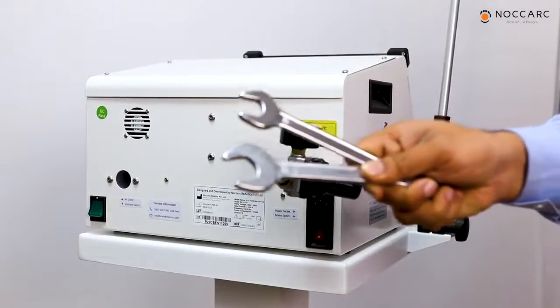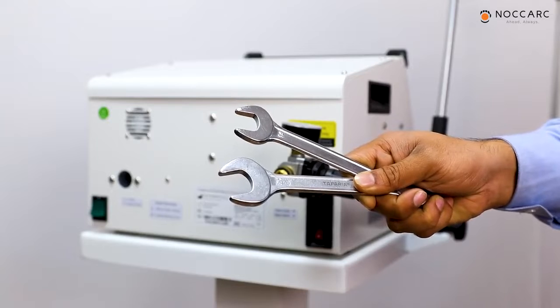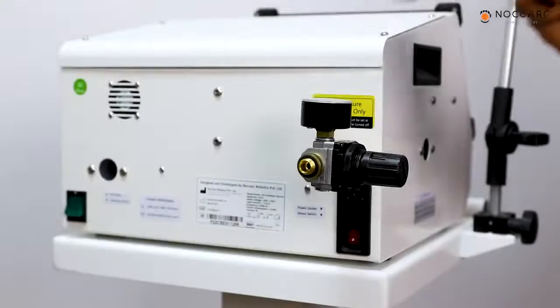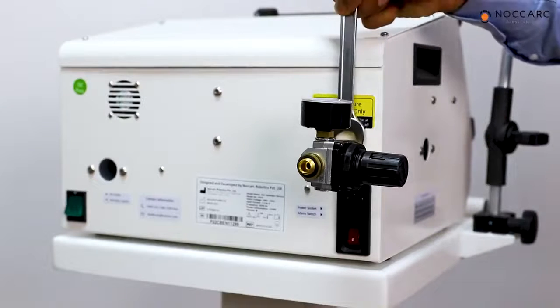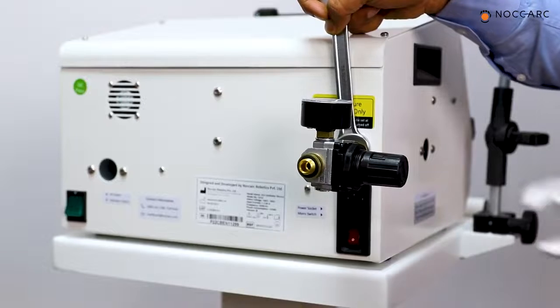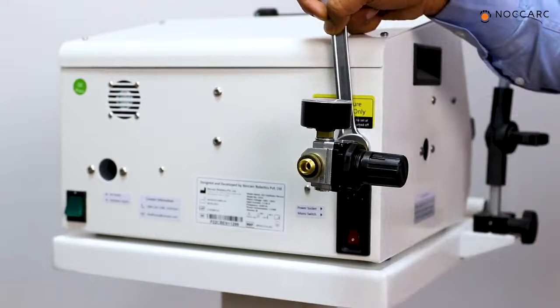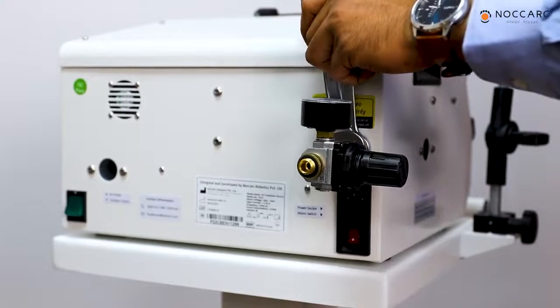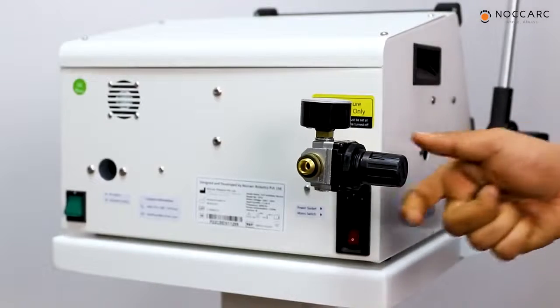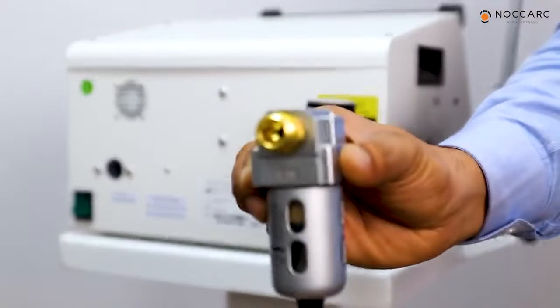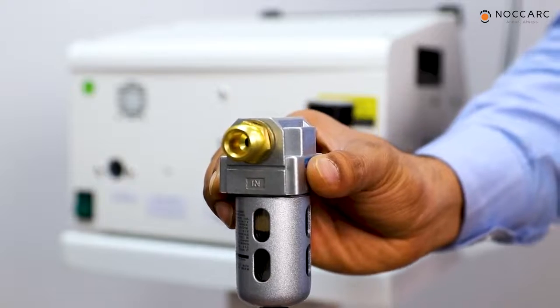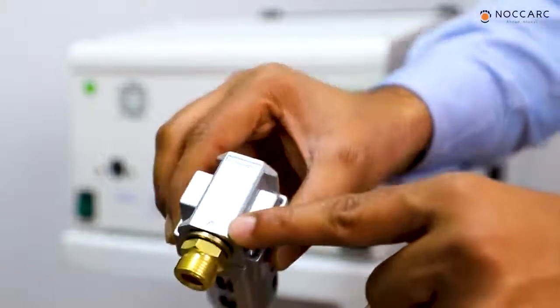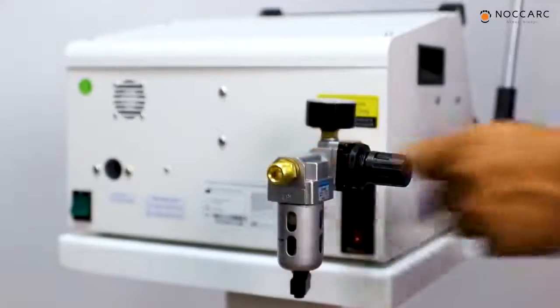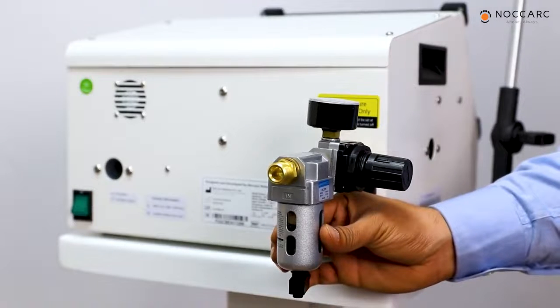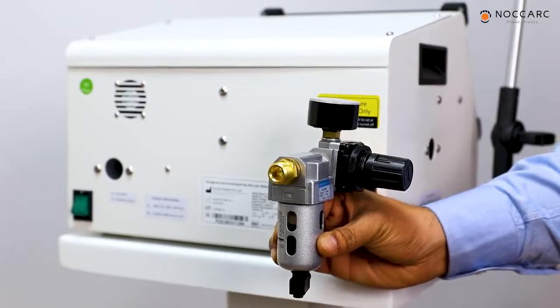Use two 18 and 21 mm spanners for proper fitment of pressure regulator. Use 18 mm spanner side at ventilator's connector. Use 21 mm spanner side at regulator connector. Ensure pressure regulator is connected firmly. Connect the oxygen inline filter to inlet of pressure regulator. Ensure this arrow mark should be towards ventilator. Ensure oxygen inline filter is connected firmly with pressure regulator.